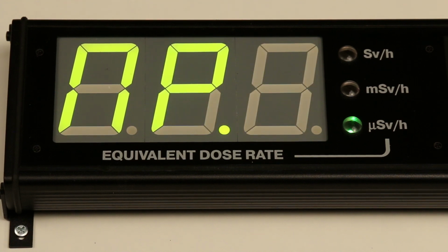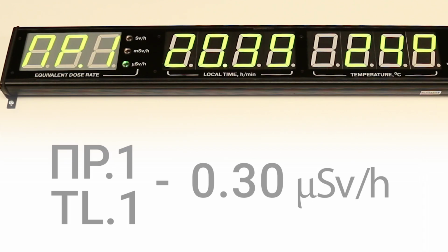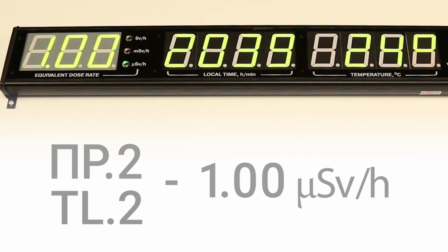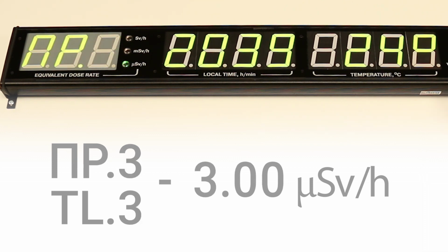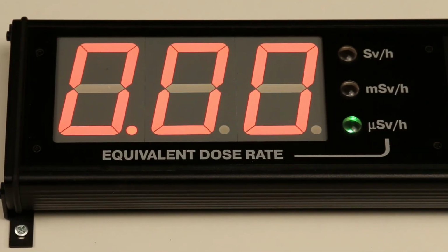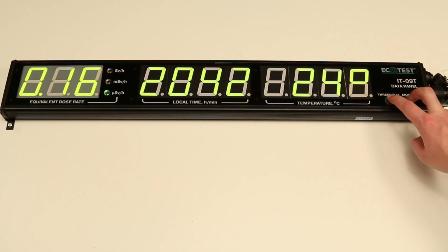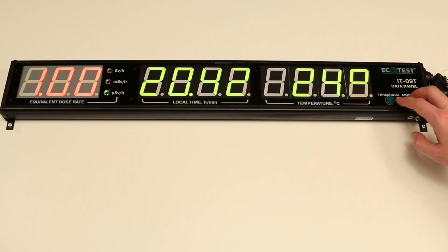When switching the data panel on for the first time, the following threshold levels are set up. The first threshold level is 0.3 microsievert per hour. The second threshold level is 1 microsievert per hour. The third threshold level is 3 microsievert per hour. A preset zero value of the threshold levels deactivates the alarm system of the data panel. When putting the data panel into operation, threshold levels must be set up in accordance with regulatory documents or other requirements.